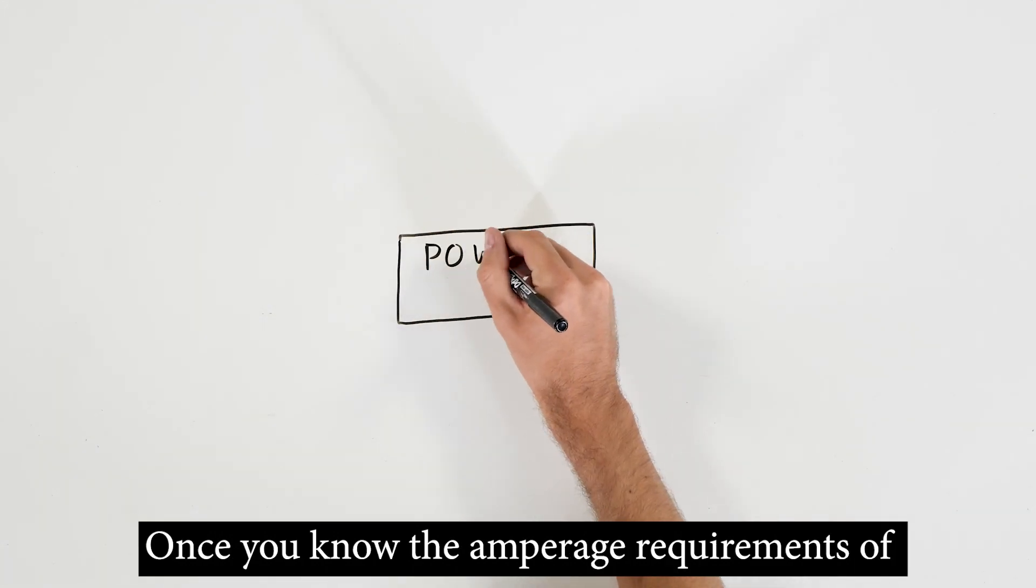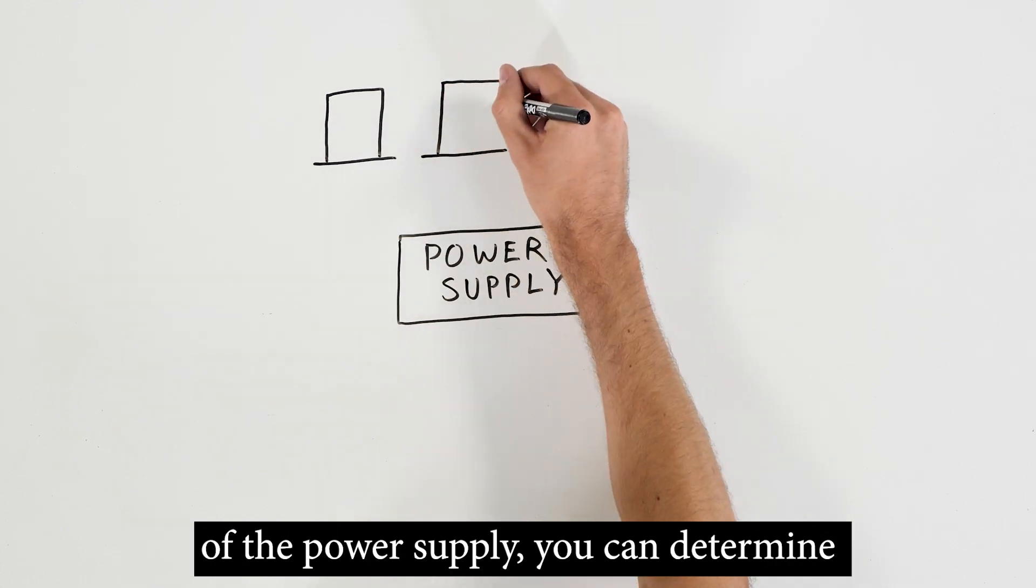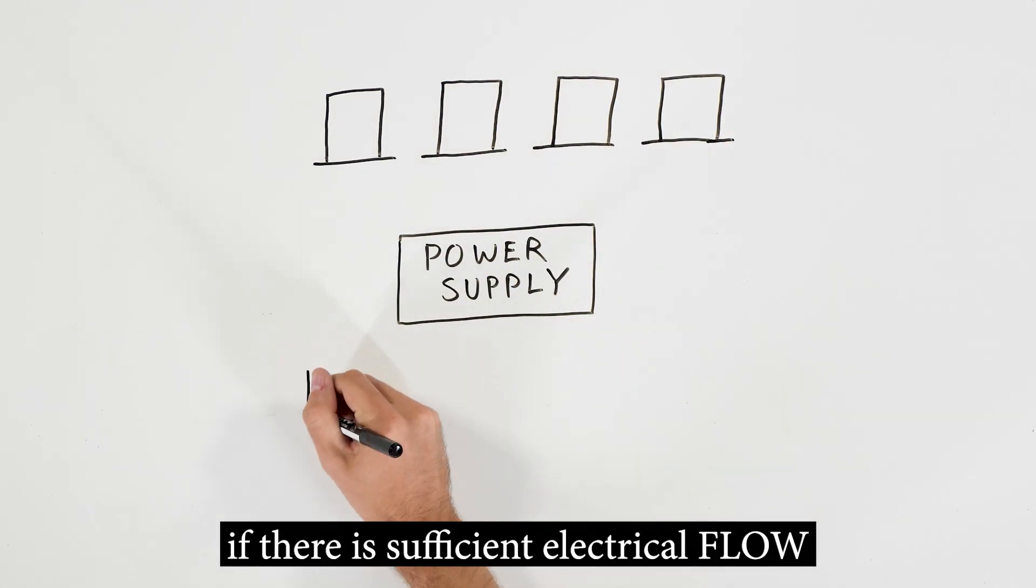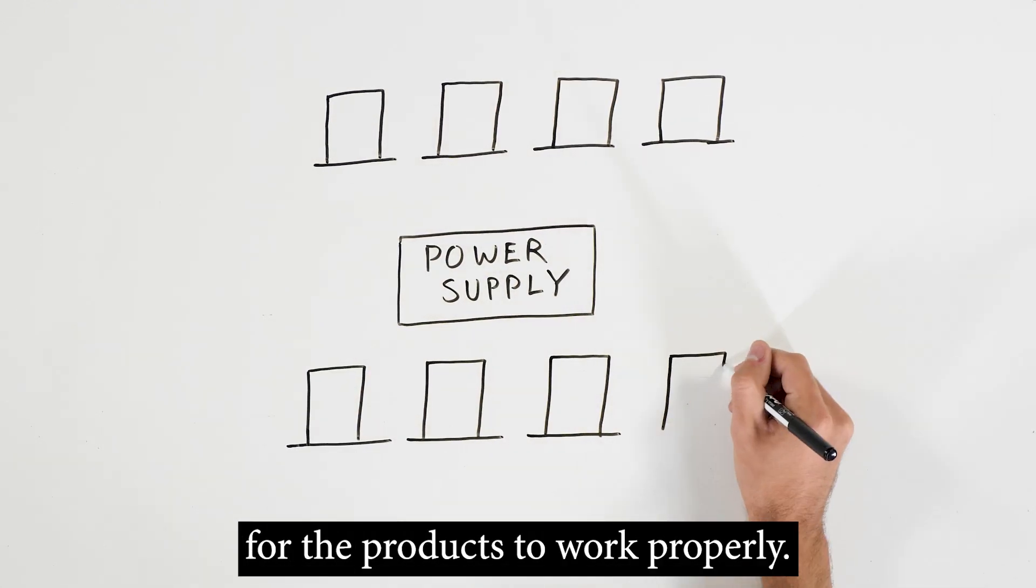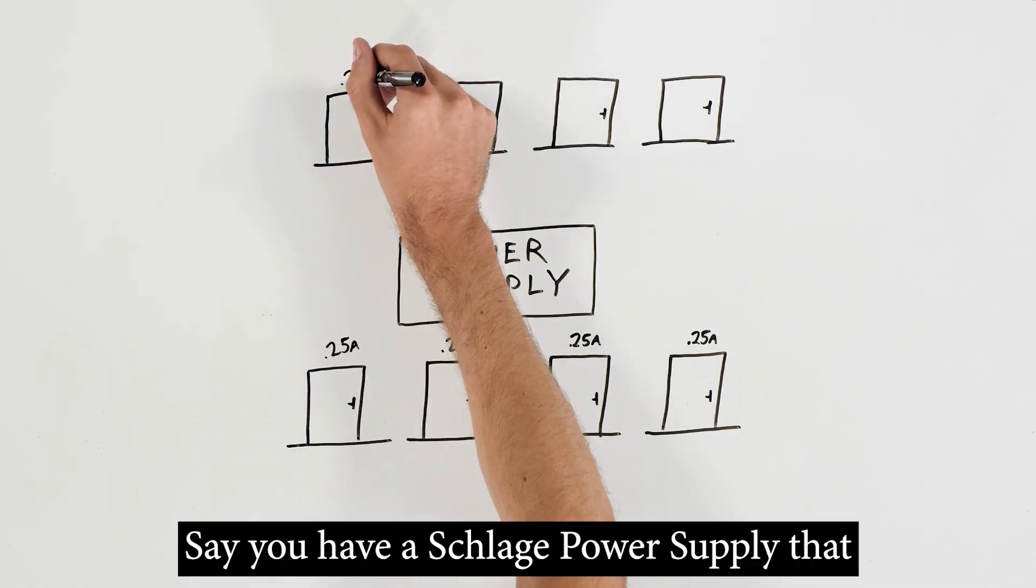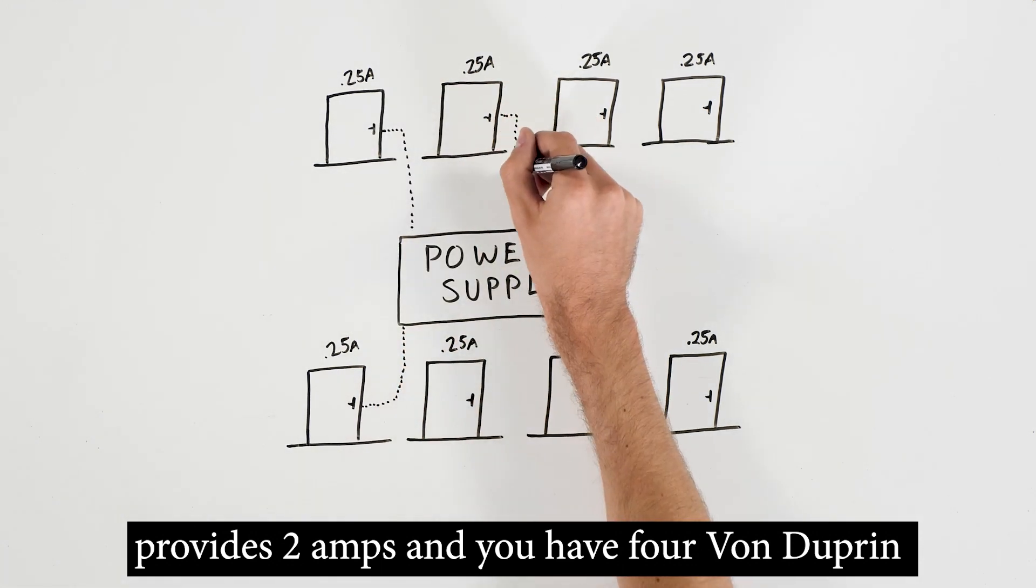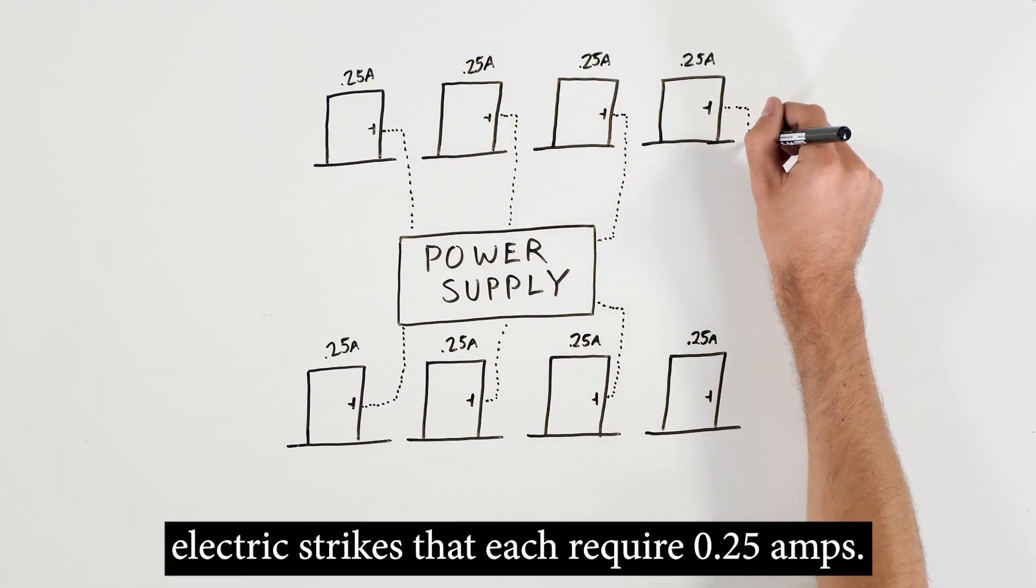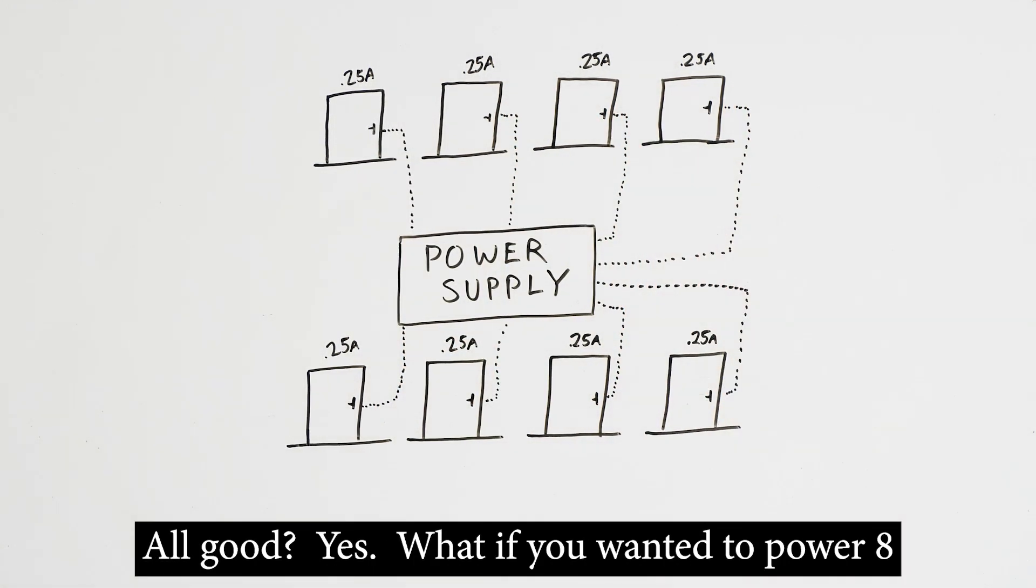Once you know the amperage requirements of the electrified products and the amperage rating of the power supply, you can determine if there is sufficient electrical flow for the products to work properly. Let's try it. Say you have a Schlage power supply that provides 2 amps, and you have 8 Von Duprin electric strikes that each require 0.25 amps. All good? Yes.